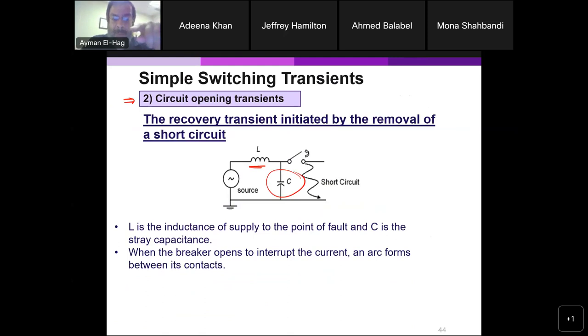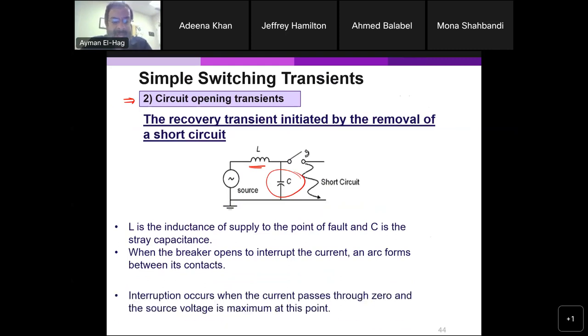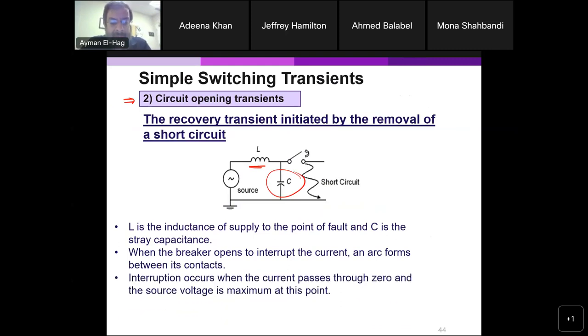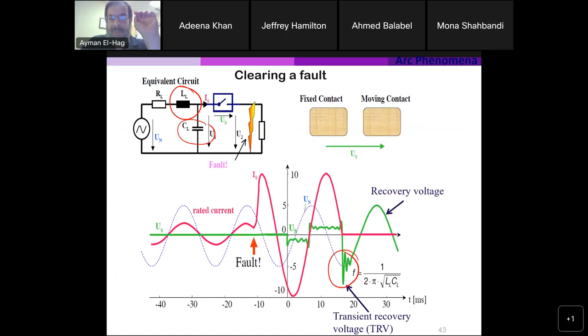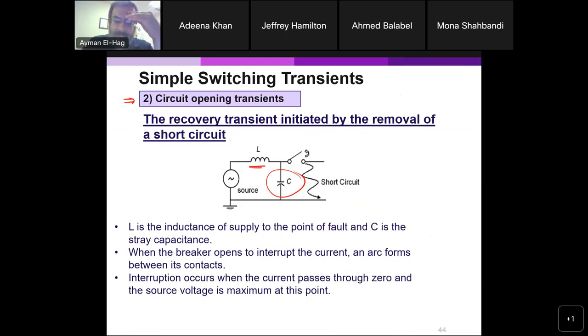Now when the breaker opens, trying to interrupt the current, the arc forms between its contacts. The interruption occurs when the current passes through zero. Always, the interruption happens when the current reaches zero. When the current reaches zero here, that is the moment, because there's no current, and remember this is an AC. So this is the moment that most likely the breaker will interrupt.